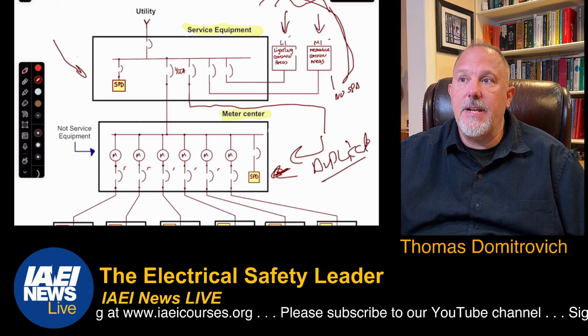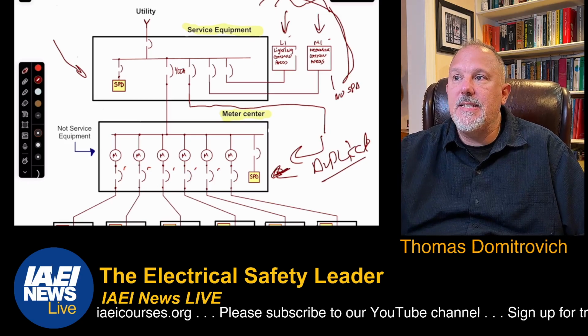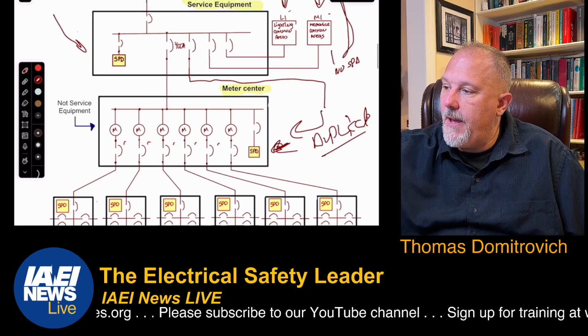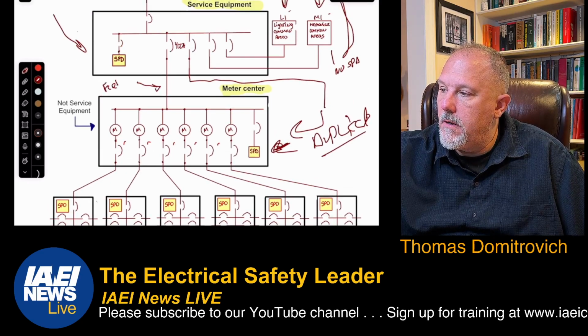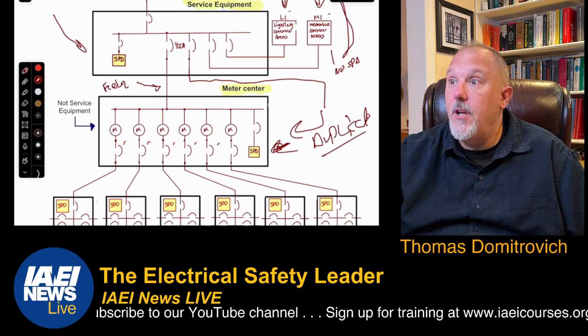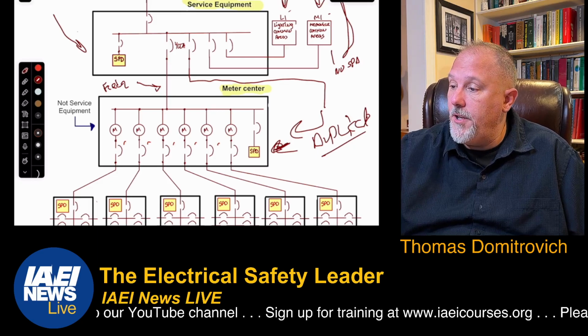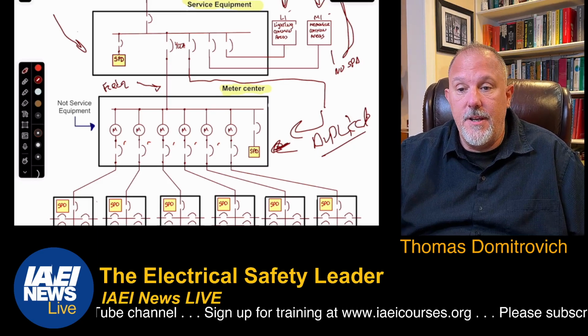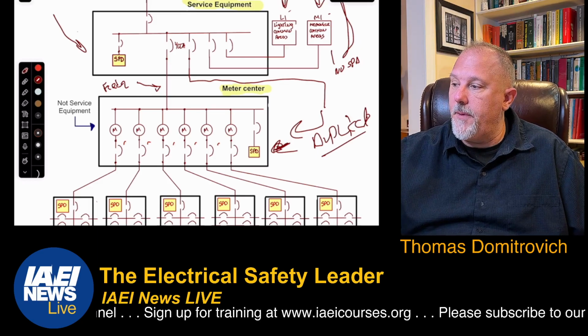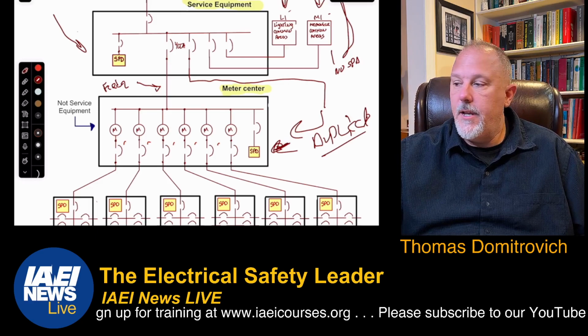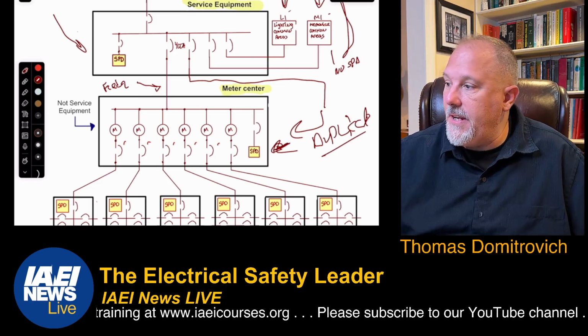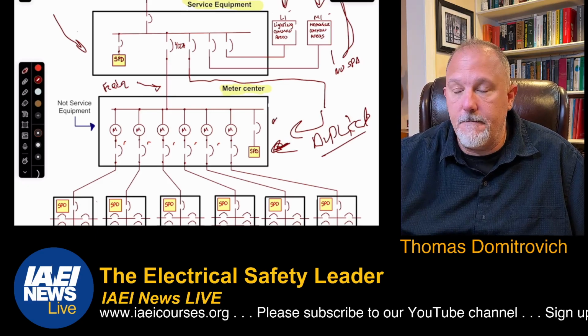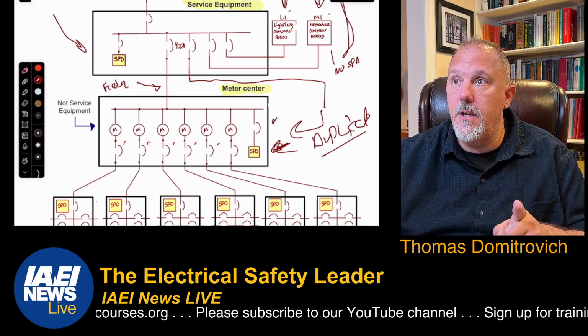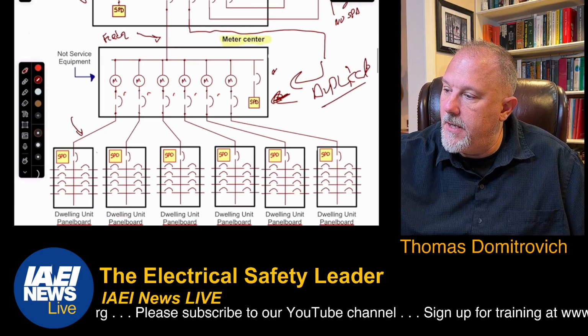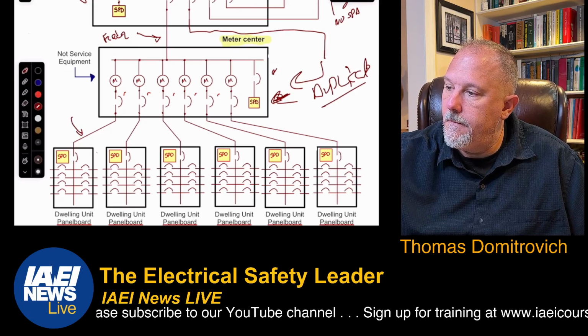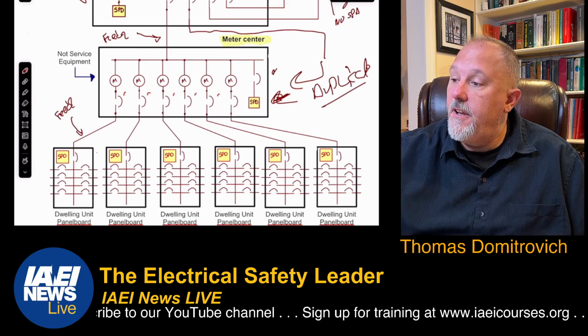215 tells us in 215.18 that a feeder that supplies any of the following, and if these are all dwelling units, so that means that feeder supplies dwelling units. It supplies 1, 2, 3, 4, 5, 6 dwelling units. So the feeder that leaves the service equipment feeds equipment that supplies 6 dwelling units. So for that feeder, you would need an SPD at the meter center to meet 215.18. And it just so happens that this feeder feeds a dwelling unit.